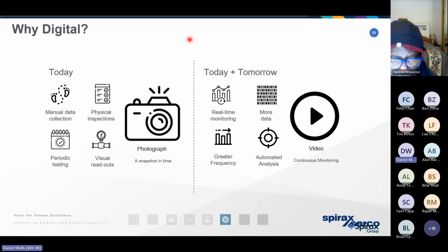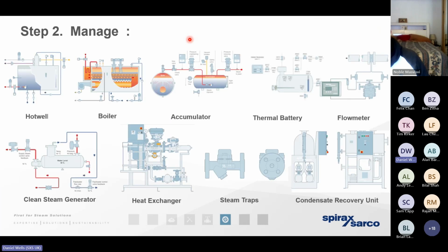That means that we can act on any inefficiencies, not just months after they've occurred, but when they're at the point of starting to become inefficient or starting to manifest themselves. We can interrogate the system to understand how and where we can modify the process to bring around further energy efficiency improvements. So we can digitalize at an asset level, or we can digitalize at a site level. Some of the assets that we can digitalize range from individual steam traps to boilers to hot wells to condensate recovery units. We can get a much, much better understanding with regards to where those inefficiencies start to exist, and more importantly, what the payback is going to be in the reduced cost of steam, cost of gas, or by reducing the carbon emissions, for example. It really depends on what our client's driver and priority is.